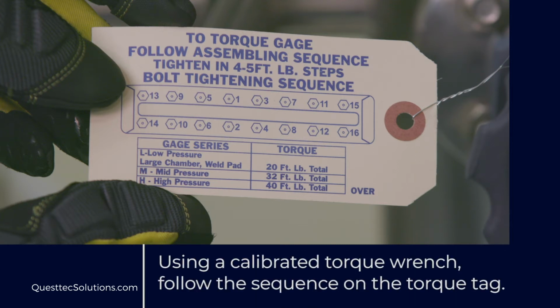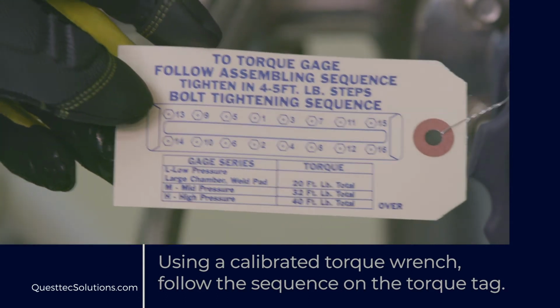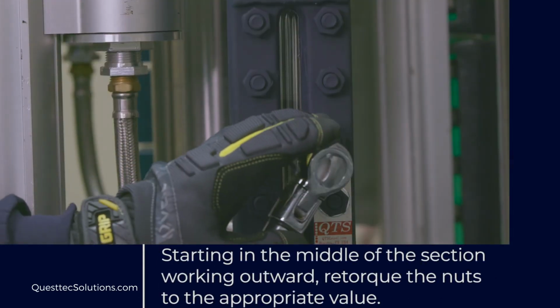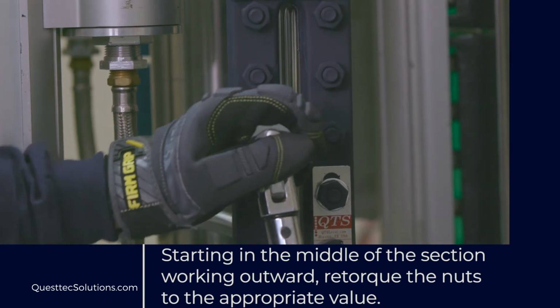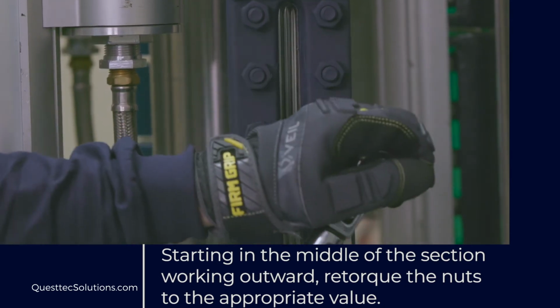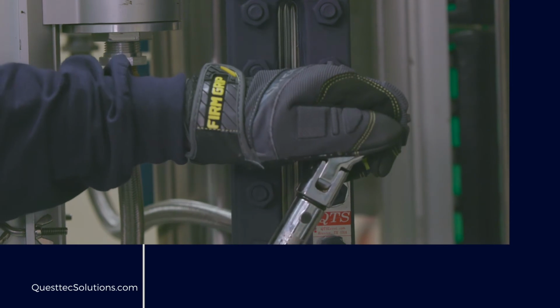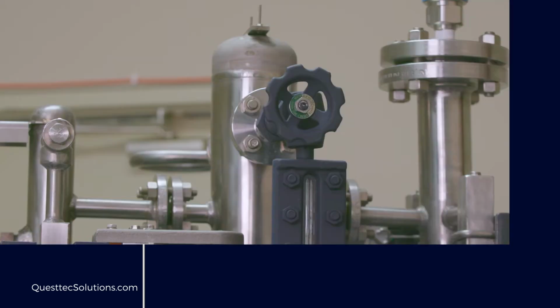Using a calibrated torque wrench, follow the sequence on the torque tag. Start in the middle of the sections, working outward. Retorque the nuts to the appropriate value. Now let's move on to startup.